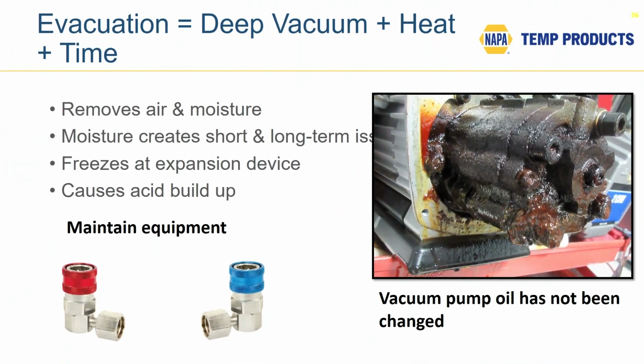Very important. And so evacuation: the reason that you pull an evacuation is that by reducing the pressure on the moisture in the system, it will boil at a lower temperature. The picture there is a vacuum pump that we used here at our training center for just one season, as an experiment. You can see the gunge and the grunge that has developed inside the crankcase of that vacuum pump in just one season. The vacuum pump oil is what creates the seal that enables you to pull a deep vacuum, so it's very important that you change the vacuum pump oil.